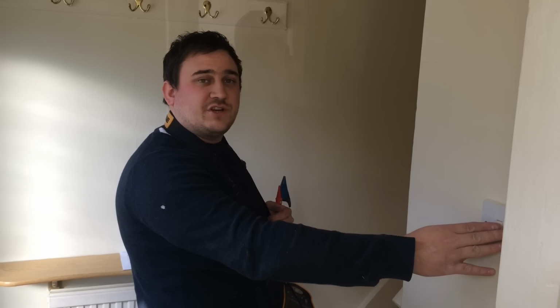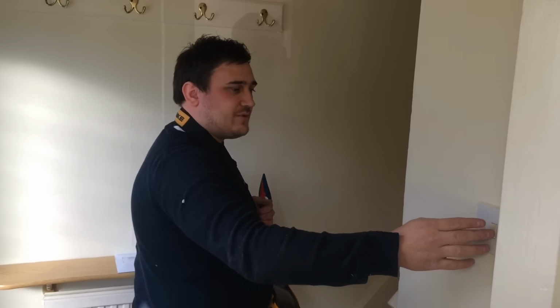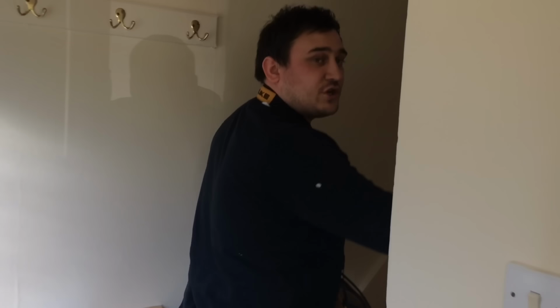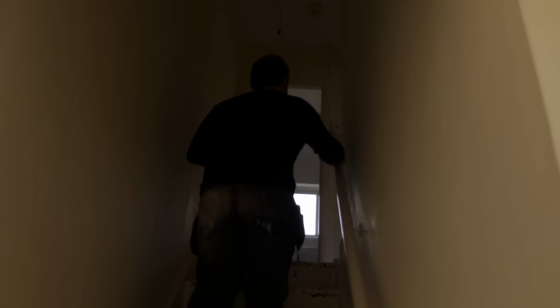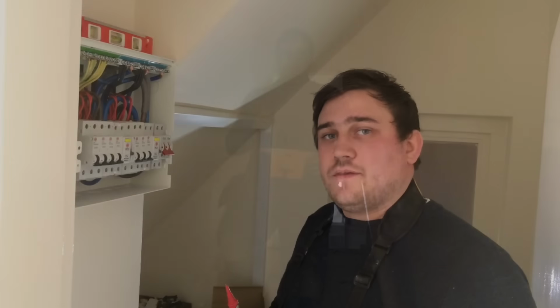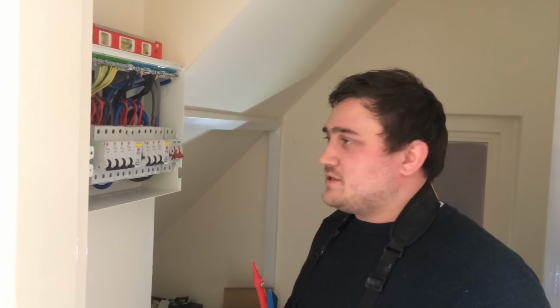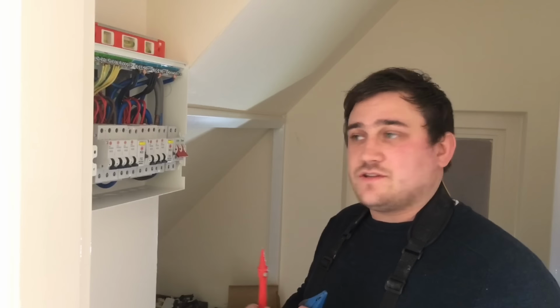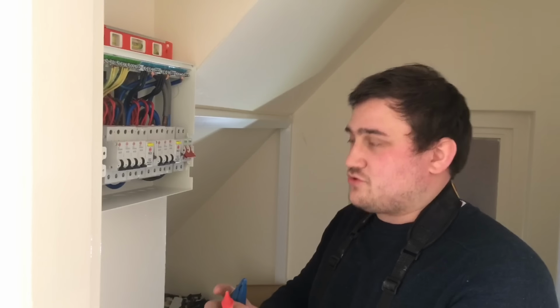We're now going around switching our two-way lighting circuit so we can check the strappers. So I'm going to switch that one, but I'm also going to go to the top of the stairs and switch this switch into the other position. Now we can retest our insulation resistance. Now we've been round and switched the strappers on that lighting circuit, we're now going to do insulation resistance just on that lighting circuit to prove the strappers.